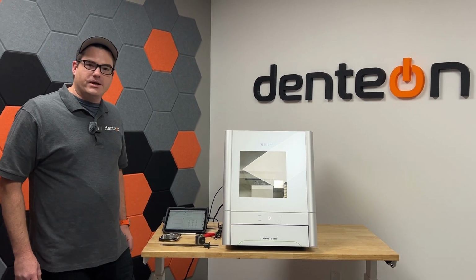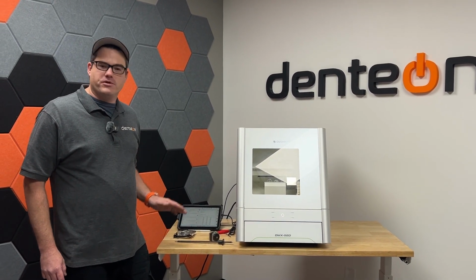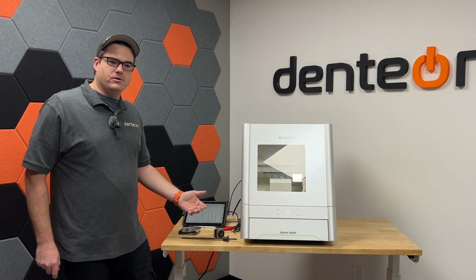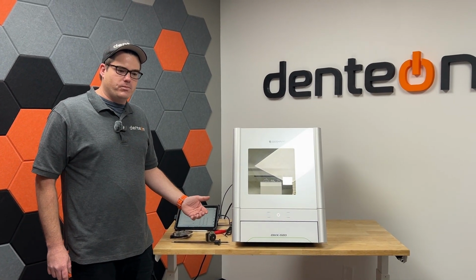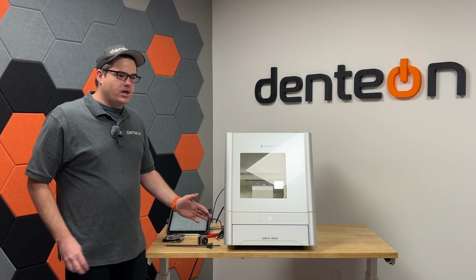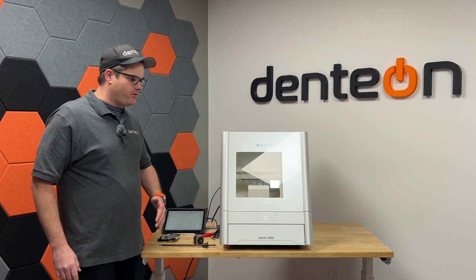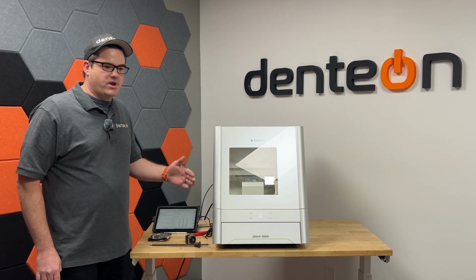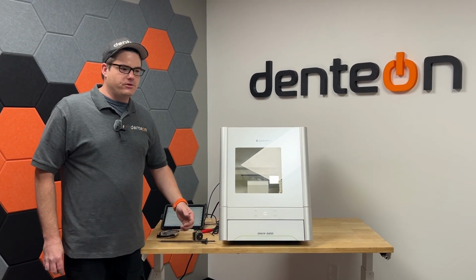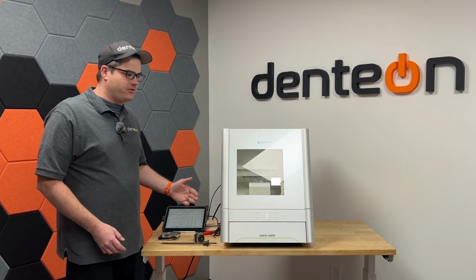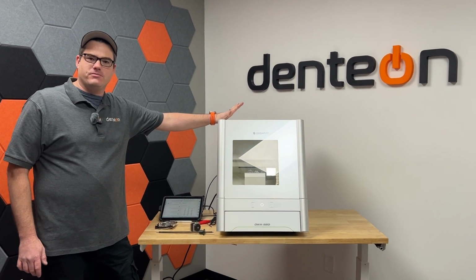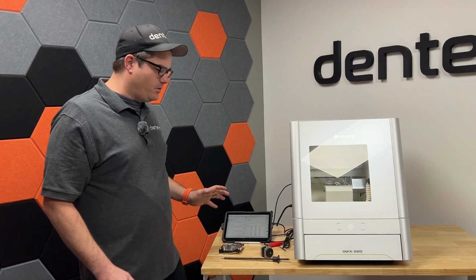All right, when we're doing diagnostics on people's machine, one of the first things that we ask is, what's your policy on calibration? And it ranges widely. It ranges from what's calibration to we do it every day, every morning. And so really what we're wanting to clarify is, when do you actually need to calibrate this machine? So in order to set this up a little bit, we're going to explain what calibration's doing.